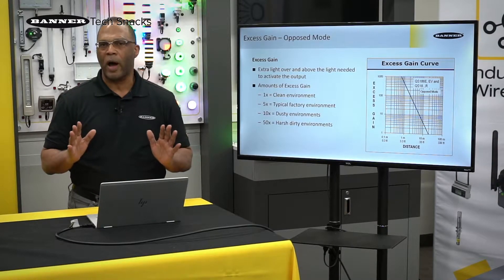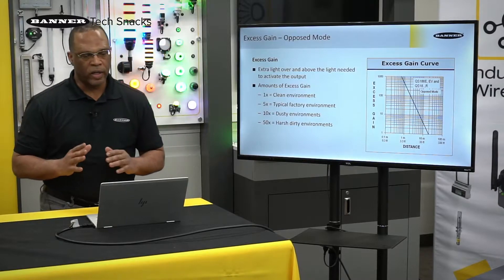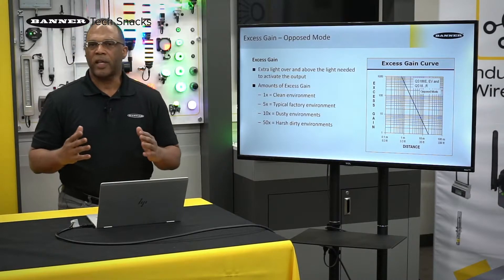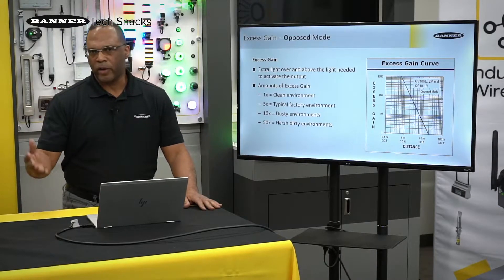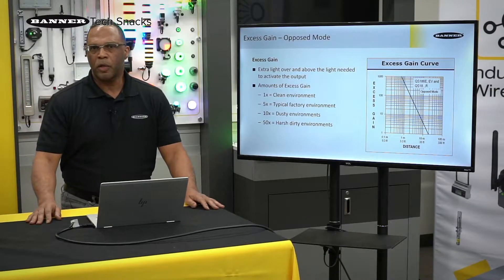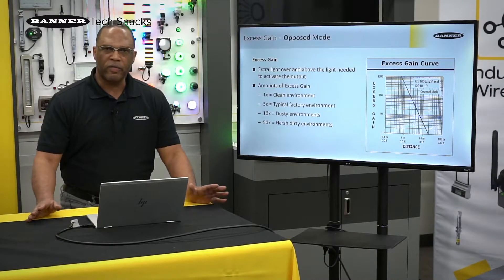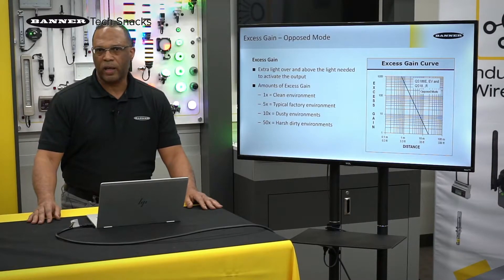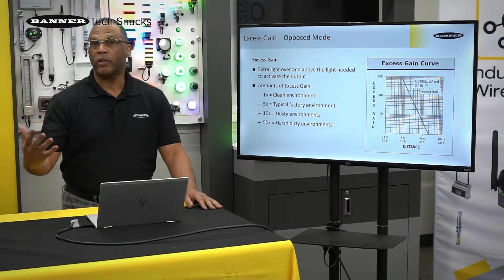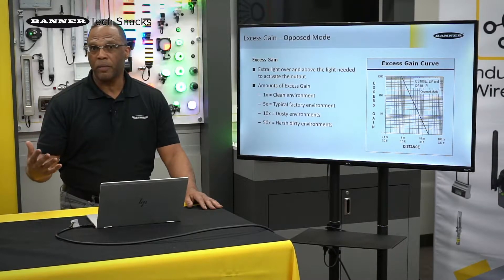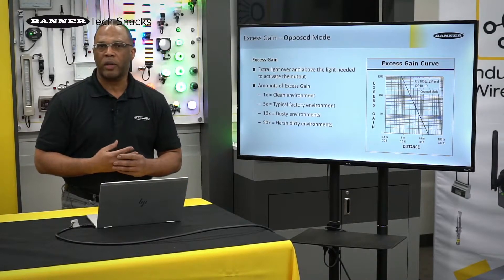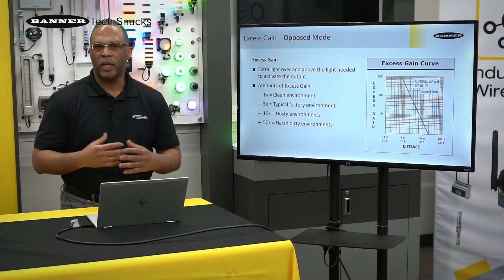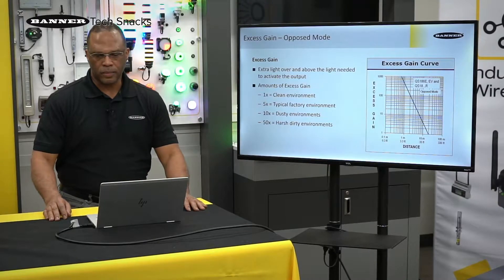That's how a sensor sees a target at one excess gain, so you never really want to operate there. We typically say if you're in a factory environment or warehouse, you want to be at about five excess gain. If you're in a slightly dirty environment, 10. If you're in a very dirty environment, you might want to be at 50 excess gain.